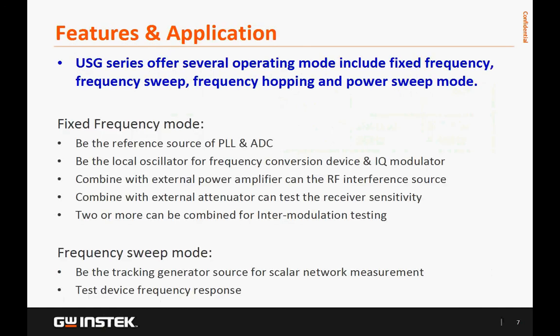The USG Series has several operational modes including fixed frequency, frequency sweep, frequency hopping, and power sweep.